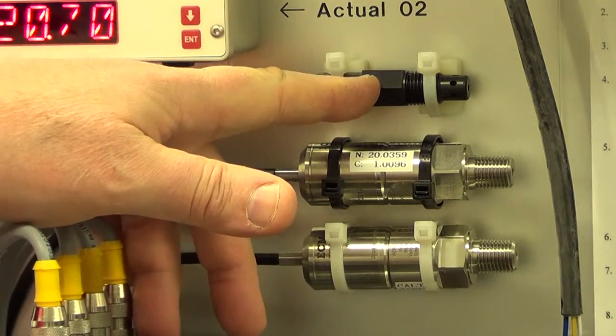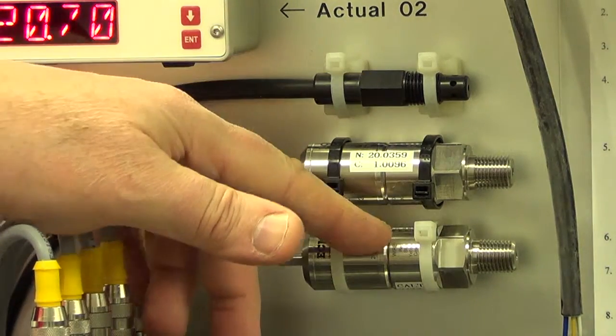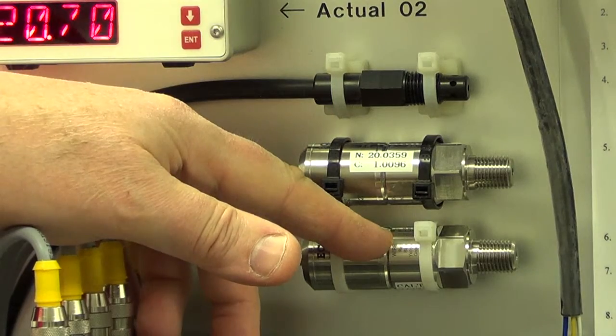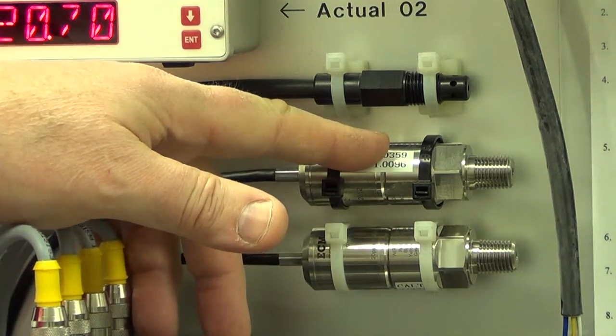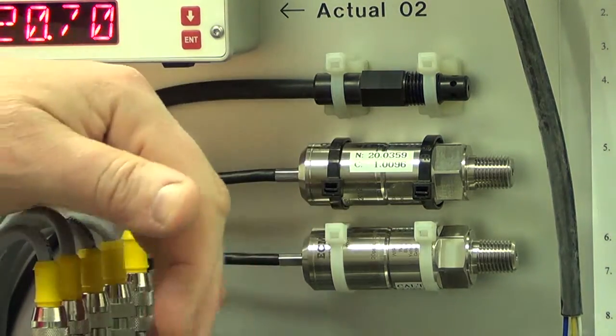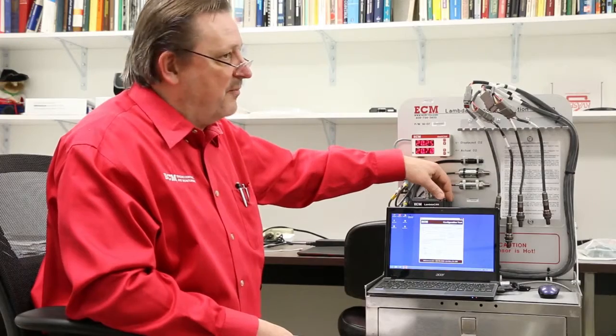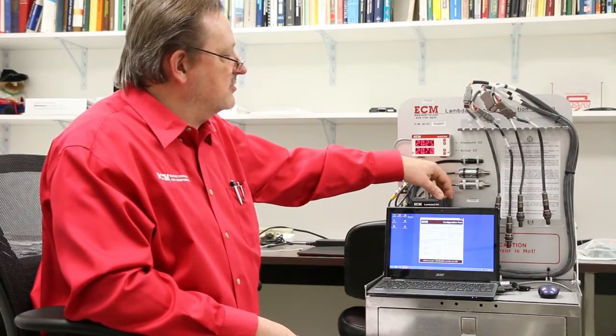The sensors that are used by the Lambda can to determine the humidity and therefore calculate a correct actual O2 is this sensor up here, which measures humidity and temperature, and this one down here, which measures pressure. This pressure sensor here is used by the Lambda cans to do the pressure compensation in case you're doing this calibration at different altitudes or different barometric conditions.